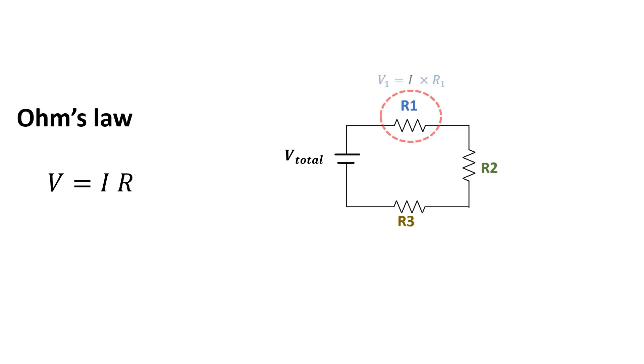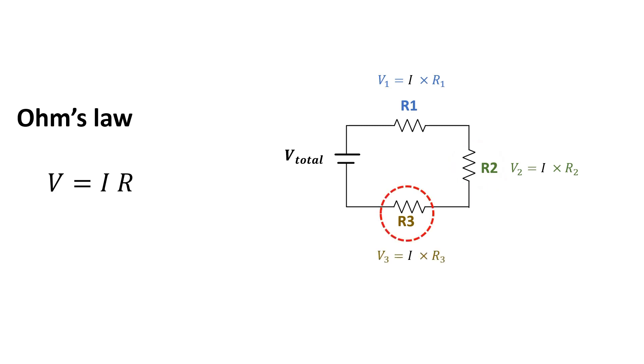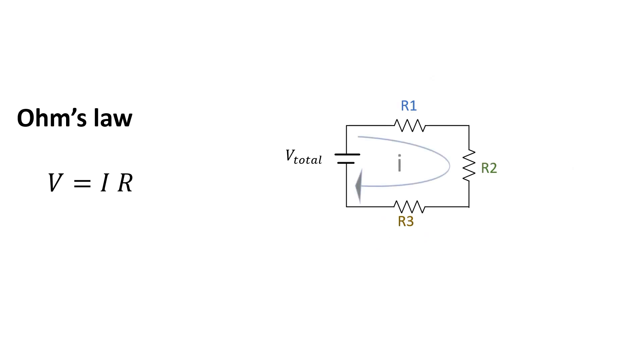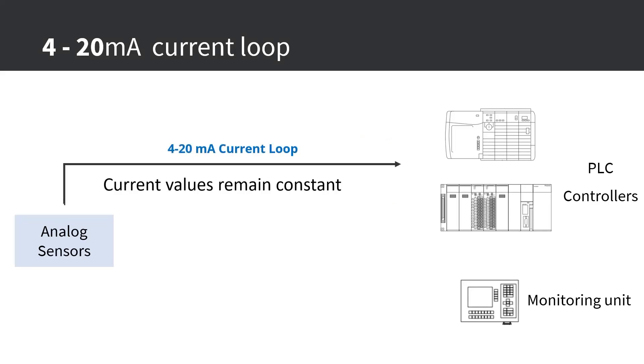According to Ohm's law, voltage equals current times resistance. If I measure the voltage across the first resistor, voltage equals current times the value of the first resistor. The same applies for the second and third resistors — meaning there is a voltage drop across each load. However, the current is the same anywhere in the loop, and this is the basis of the industrial 4 to 20 milliamps current loop circuit: the current values remain constant and don't drop or change over long connections the way voltage values do.